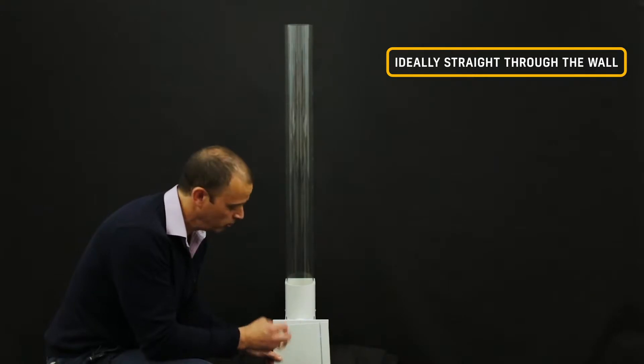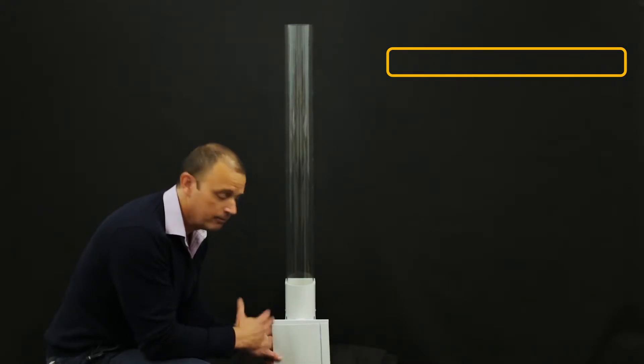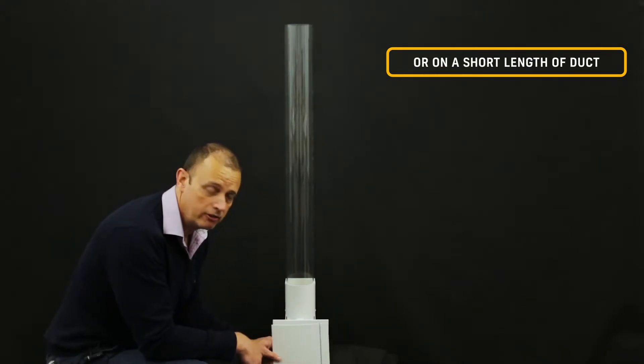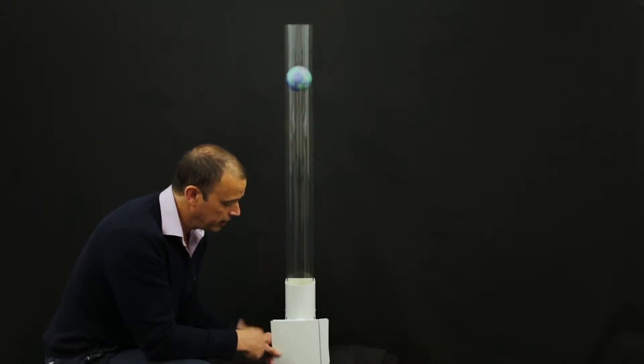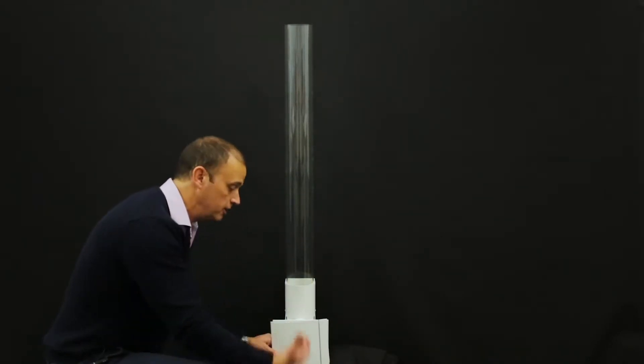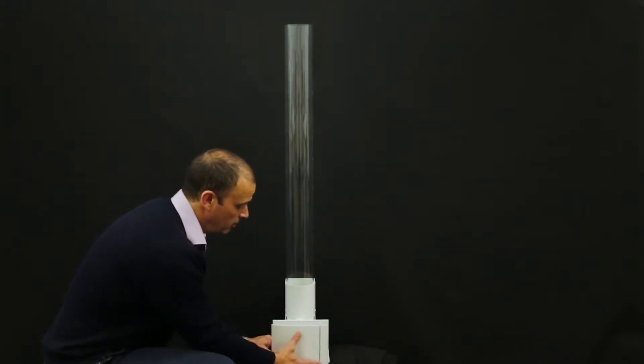So this fan wants to be mounted straight through a wall or on a short length of ducting, maybe a meter of rigid duct or anything like that. If you start installing it in a complicated system or a lot of flexible duct, it's not going to cope with it. You need to go to the other fan.